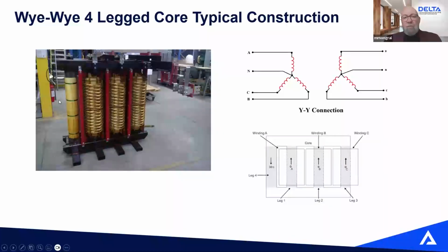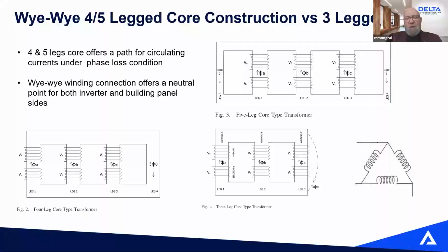Why do we have to do those types of core? Mainly, we're going to build a transformer based on the requirement of the inverter. So if you have a building with 3-phase 4 wires, the transformer needs to have 3-phase and the neutral, so a Y connected transformer. And if your inverter is a 3-phase 4 wire system, again we need a Y connected winding. So we end up with a YY transformer. And there's many ways to build a YY transformer. We can build a YY transformer on a standard 3-legged core like this. We can also do 4 or 5-legged core. Again, we don't decide. Usually it's the inverter manufacturer that will recommend, or will require, a specific type of core.